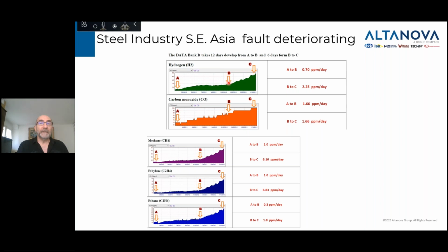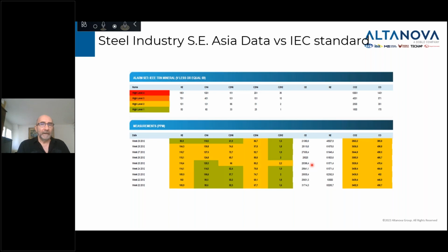So again, the accuracy of the measurement is absolutely critical, not just to do the diagnostic, but even to see the behavior over a period of time of those gases in that key transformer. So when you take that data, you enter it in the software, which analyzes it using the IEEE C57.104-2008 standard with different levels. You can see visually right away which gas has exceeded condition 1 or condition 2.